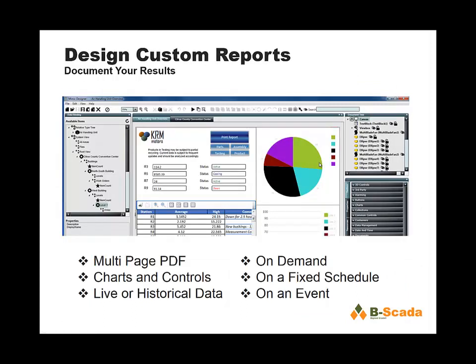The Mimic Designer can also be used for creating reports. Maybe you would like to generate a multi-page PDF document with a title page and several pages giving you information on your system. Any screen you design in the Mimic Designer can also be used as a page within that multi-page PDF document. Screens can show real-time data or historical data and statistical information like averages. Those reports can be generated on demand, on a fixed schedule — for example, every day at midnight emailed to management — or generated on an event, such as when a value goes out of range.